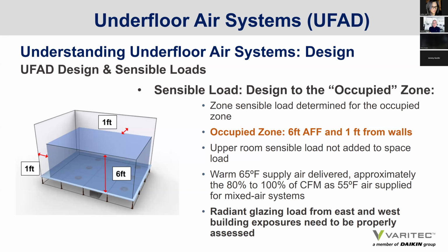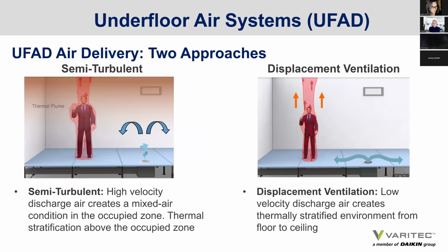When using underfloor air, one should be aware that if you have an east-west exposure and glazing, there's a radiant load that will heat up the floor. And so you have to pay close attention that you're assuming the appropriate radiant load on that direct sunlight effect on those exposed areas with large areas of glazing.